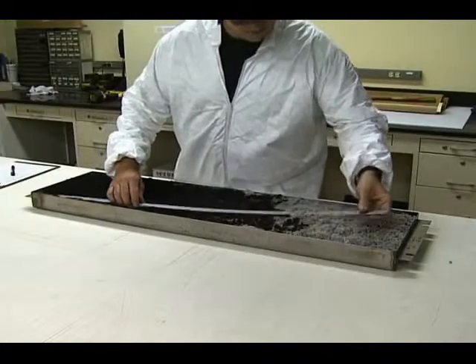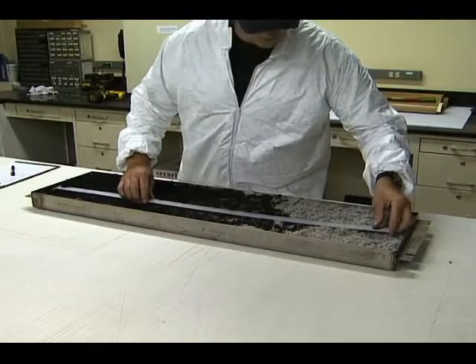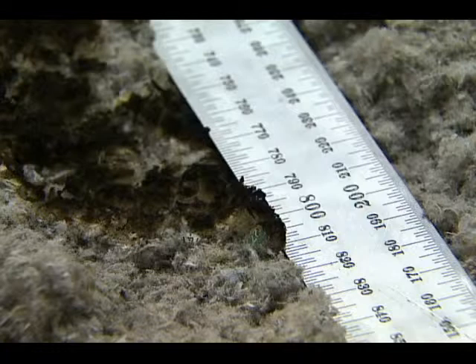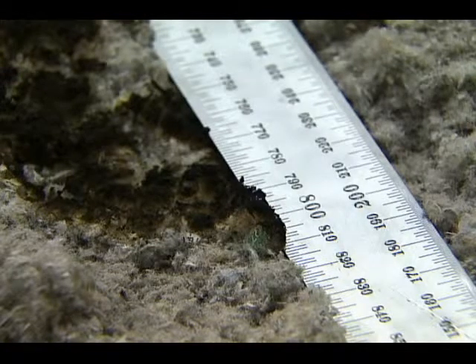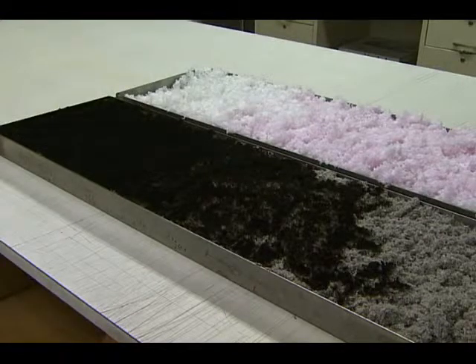Here's the most remarkable result. As you can see, the flame has traveled down the cellulose-filled tray 800 millimeters. Believe it or not, this is still a passing performance. Despite the fact the majority of the cellulose was blackened and was smoking, it still passes the current ASTM standard.